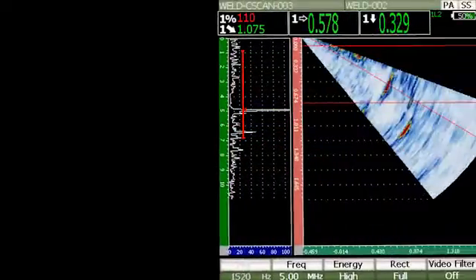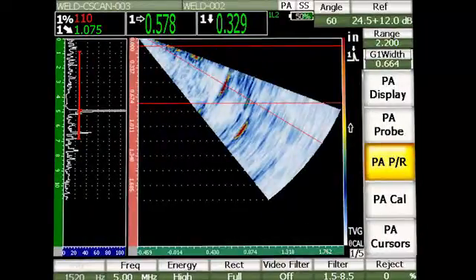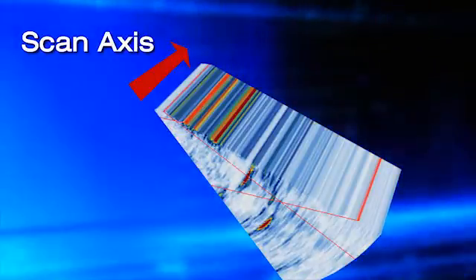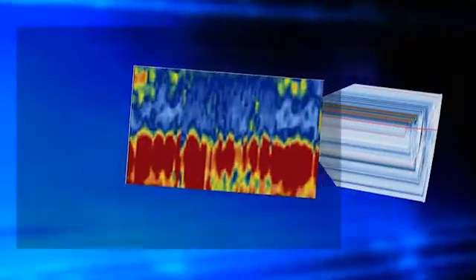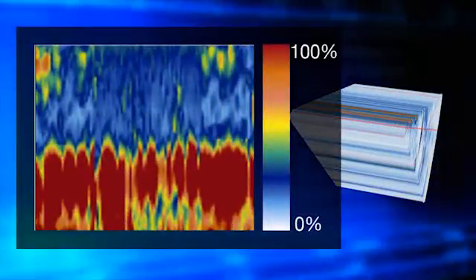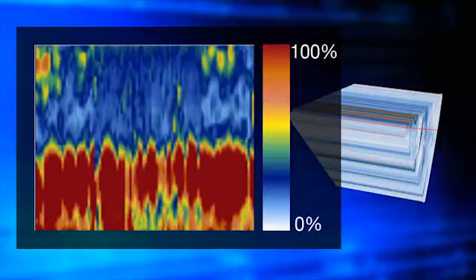A phased array encoded C-SCAN starts by electronically creating either a sector or linear scan at a fixed probe position. The probe is then moved along the scan axis, using an encoder to track its position. Depth or amplitude data for the gated region is collected at each probe position and represented using a color scale.